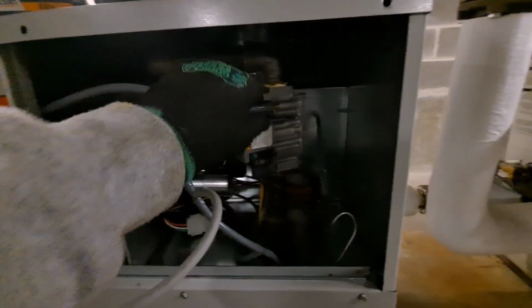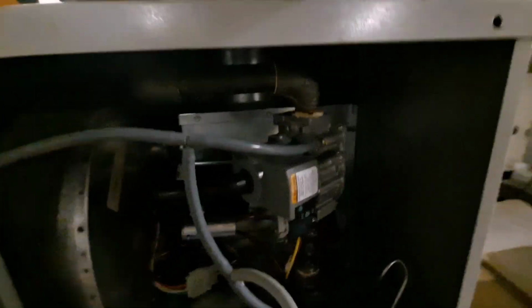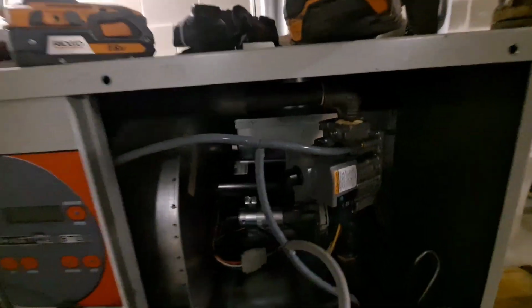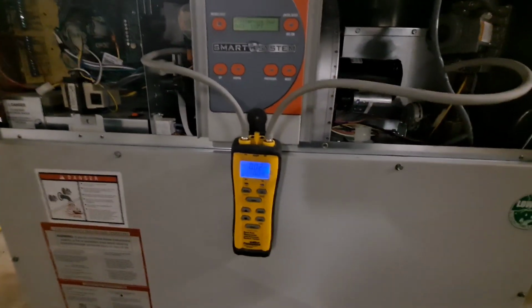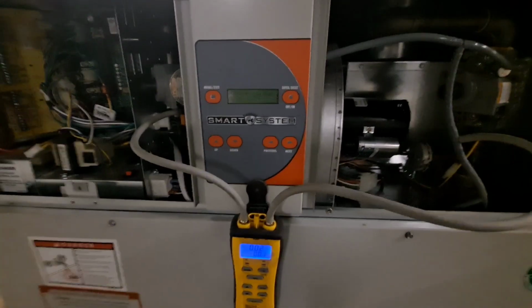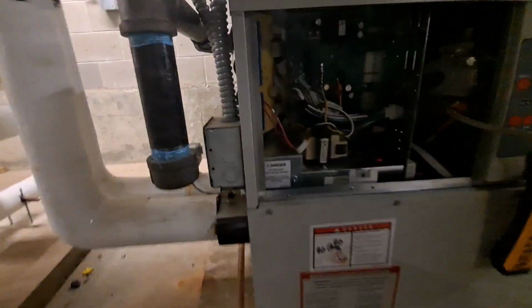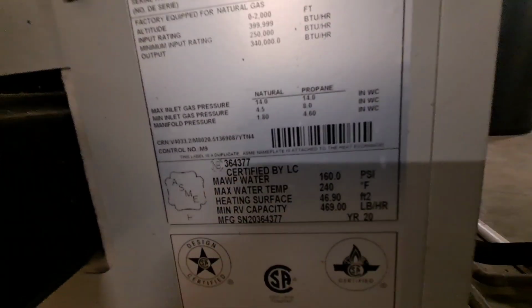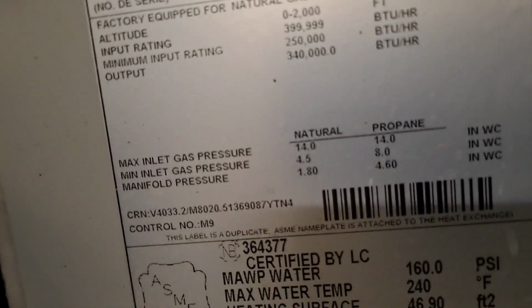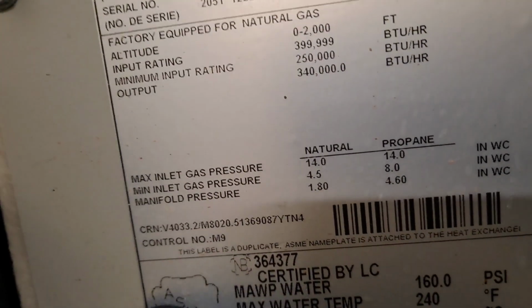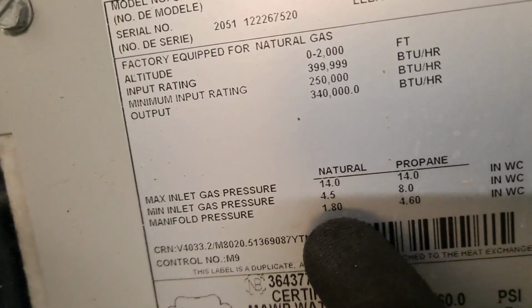So, I mean, you could technically probably pull that off and it would be fine, and it would use whatever the pressure up here in this upper area as its reference pressure. But yeah, this is how you set and adjust your gas pressure. So, and according to the tag, let me see, let me zoom in. I am on natural gas, 1.8 inches.